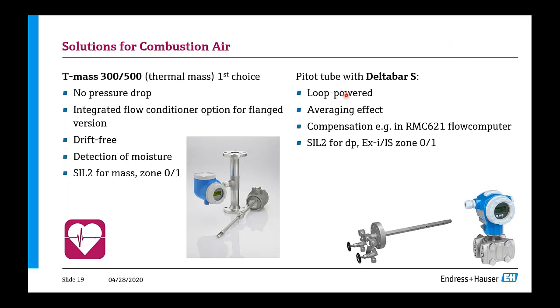Pitot tube with the Deltabar S, that's loop powered. You've got an averaging effect, and it's compensated, for instance, in an RMC 621 flow computer by pressure and temperature. Also, this comes with SIL2, however, not for mass, for the DP only. So if you need SIL2, then you need SIL2 also for pressure and for the temperature.